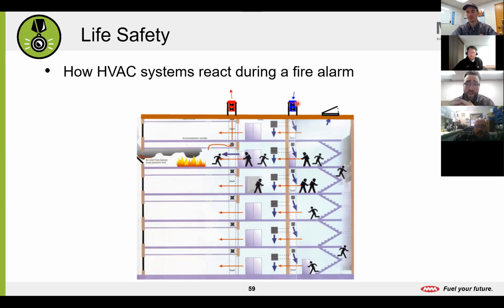But just know it is important equipment, even if you do have nuisance issues, like I said, fire dampers getting stuck or what have you. It is extremely important to the building. It's something that we want to maintain. We want to make sure it's working. And there's obviously a little bit of coordination involved, but if it's not on your radar, please make sure it is.